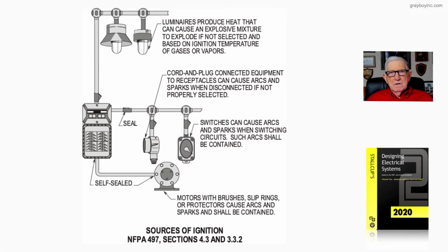Now let's review this figure 21-15. And before we do, I would like to take time to read something from NFPA 497, sections 4.2 and 4.3. And it basically states that the following three basic conditions shall be satisfied for a fire or explosion to even occur. Number one, it states a flammable liquid, vapor, or combustible shall be present in sufficient quantity mixed with air so that an explosion could occur.